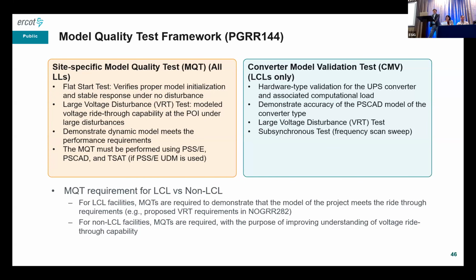As far as performance requirements, all large computational loads must meet the performance requirements in the Nodal Operating Guide, Section 2.15, which was proposed in NOGRR 282. But non-LCL, so other traditional loads, are required to submit a model quality test, but they are not required to meet the performance requirements. Okay.